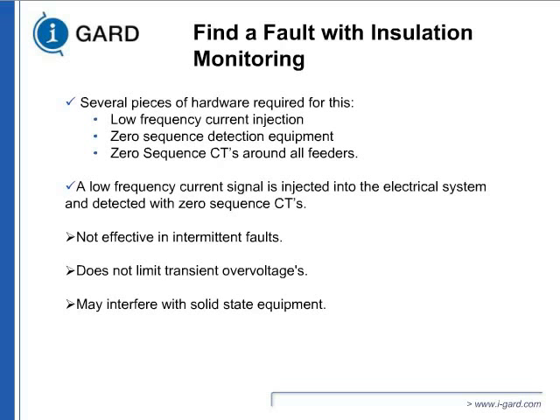So as soon as the insulation damage happened, current increased, and it gave you an alarm. But it could not detect the intermittent faults. It does not limit transient overvoltage. And one of the main problems we found with this technology was that it was causing a lot of interference with our solid state equipment.